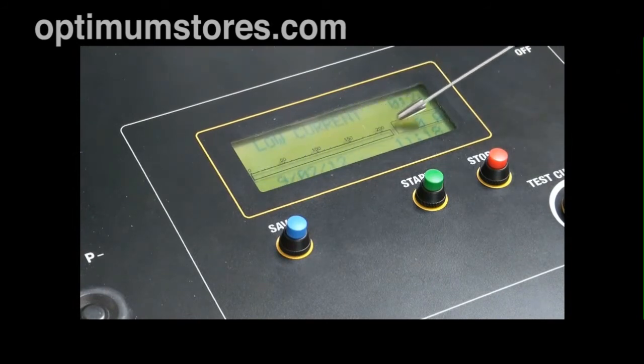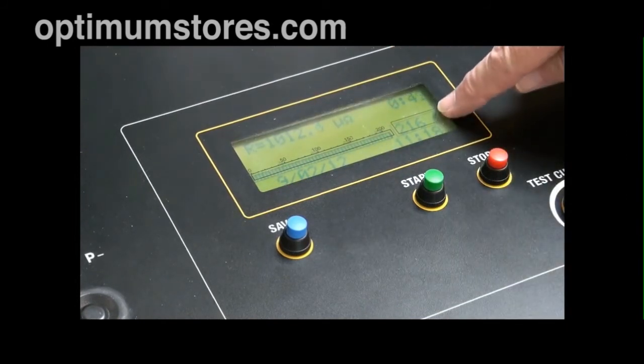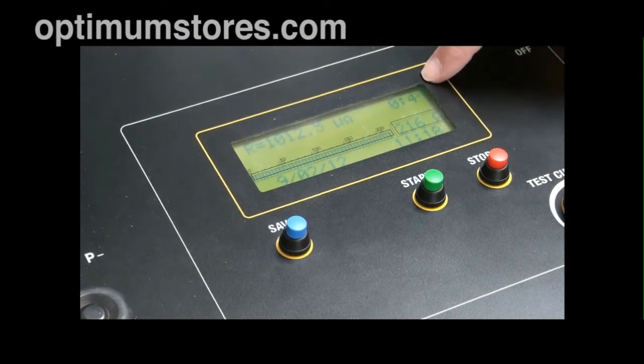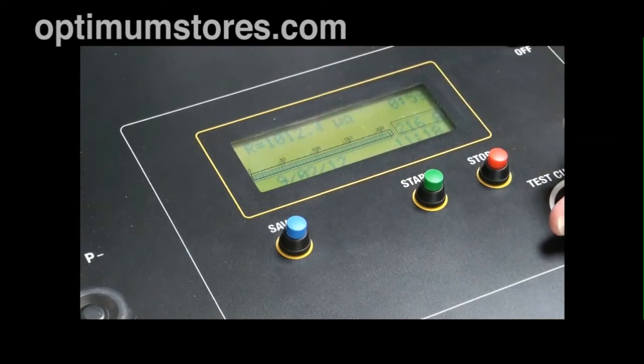We are now going to start to increase the current, and you'll see the gas gauge effectively go up. Our test specimen will get the full 200 amps, and it tells us it is a 1 milliohm, which is our test specimen rating. It tells us what our current is, and how long we have had the current applied to the device, along with the date and time stamp. That is how simple and easy it is to do this test, and I'm going to turn it off now.